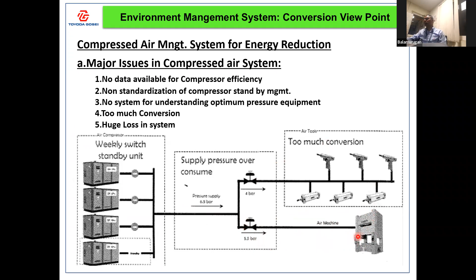Example, we have 90, 87, 95, 92 percent efficiencies. How are you going to have a standby of low efficiency compressor? Use a high efficiency compressor, generate at, for example, X bar or 4.5 bar, supply reduced to 4 bar, and use it for different equipment. And if any small equipment needs a higher pressure, go with a local air booster.